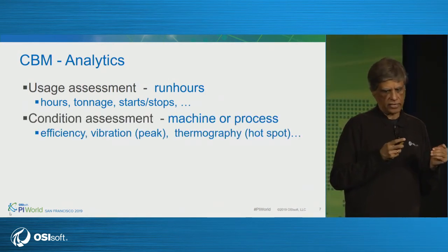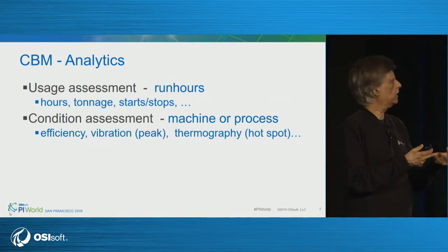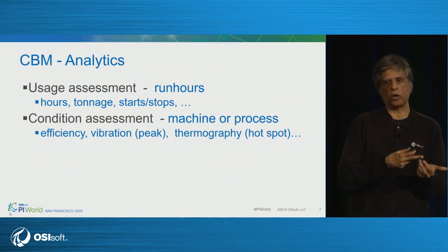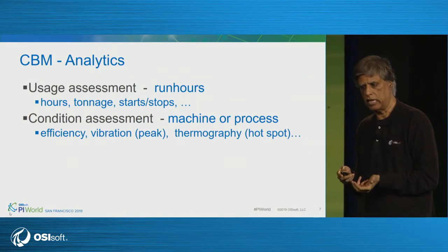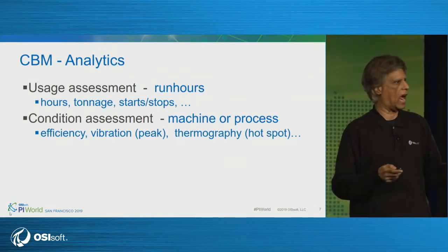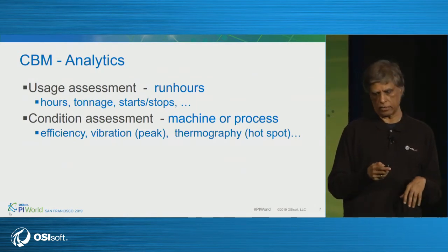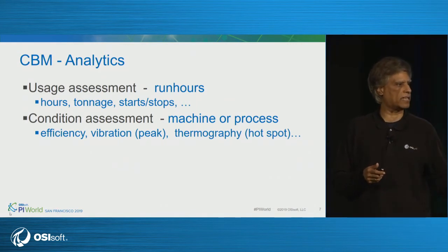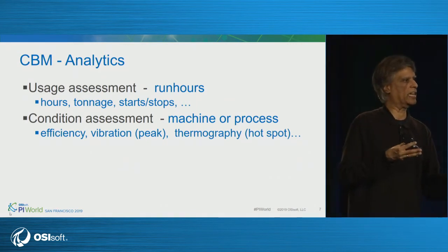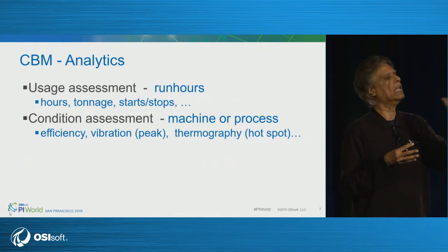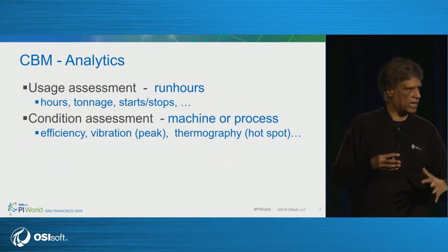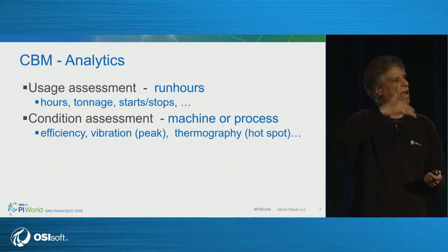Condition assessment could be about machine condition — indicators like vibration or thermography for hotspots — or it could be about process condition, like calculating heat exchanger fouling. There are calculations you can do, or you can use proxies for that.